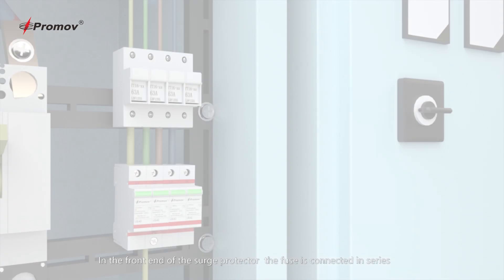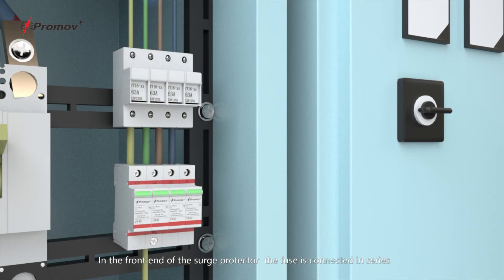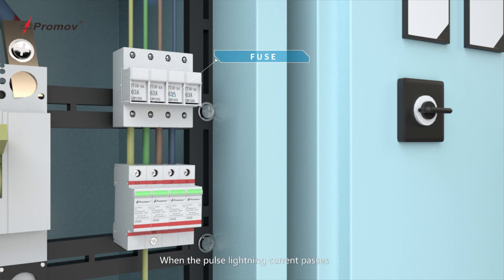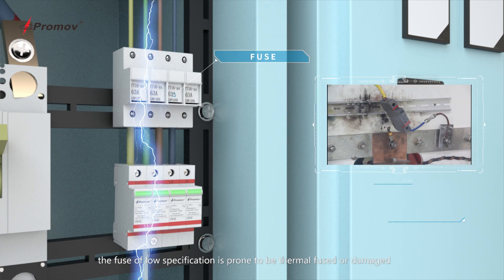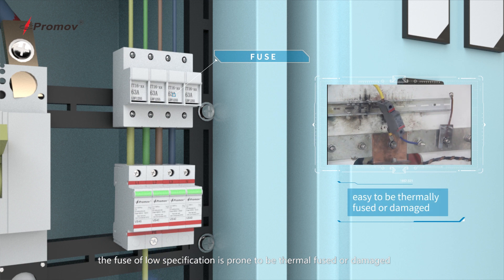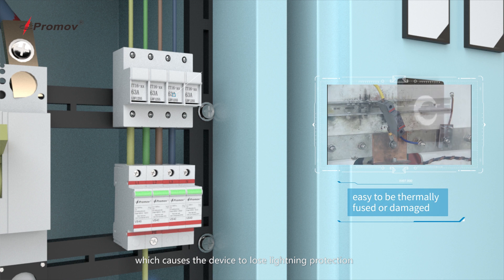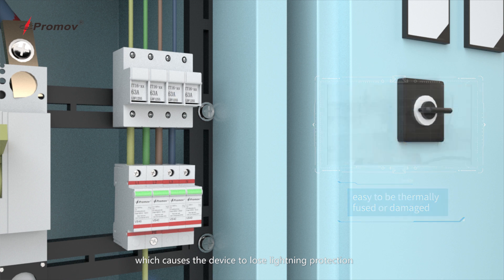When a fuse is connected in series at the front end of the surge protector and a pulse lightning current passes, a fuse of low specification is prone to thermal fusing or damage, which causes the device to lose lightning protection.